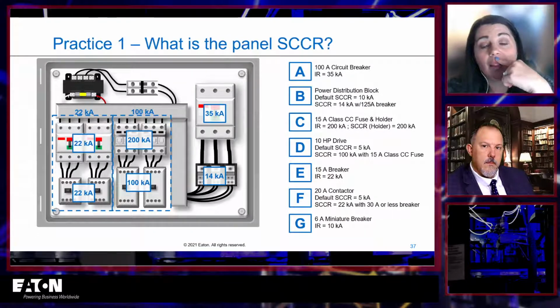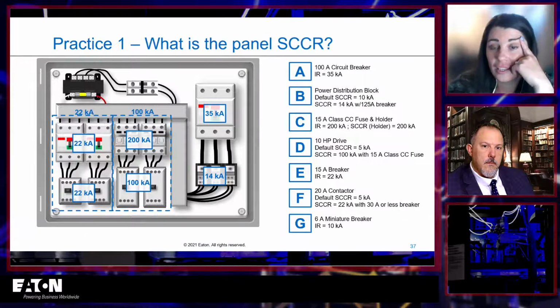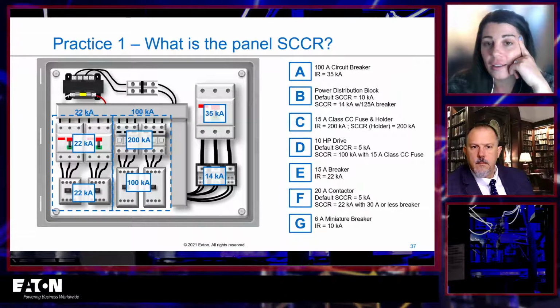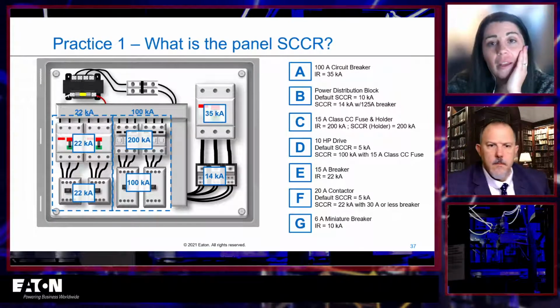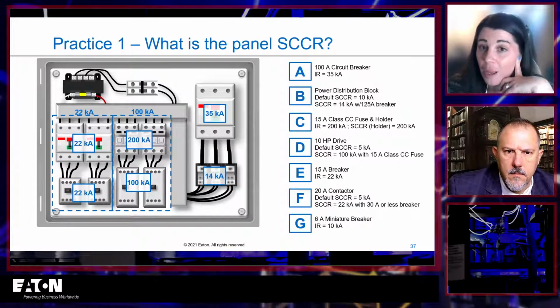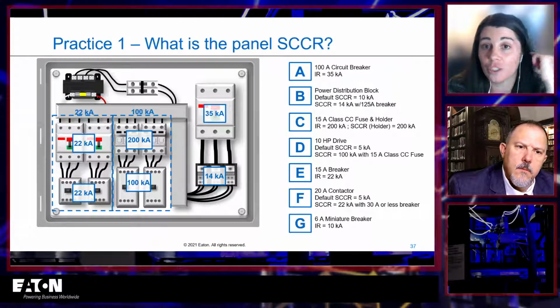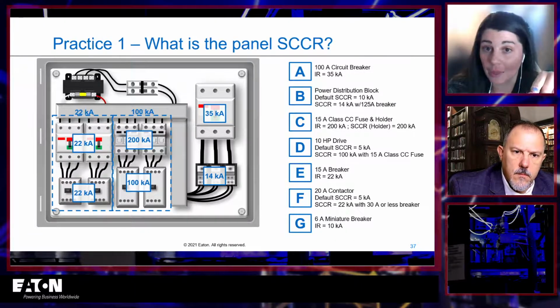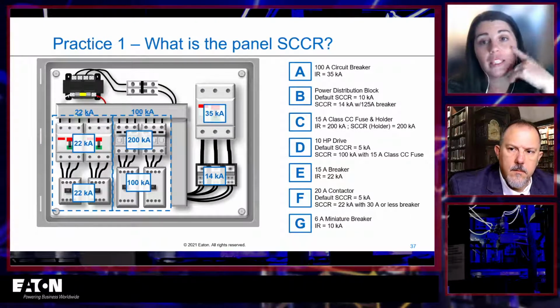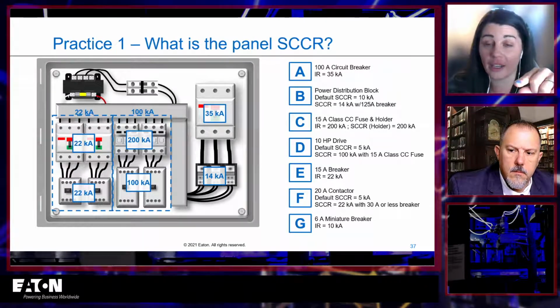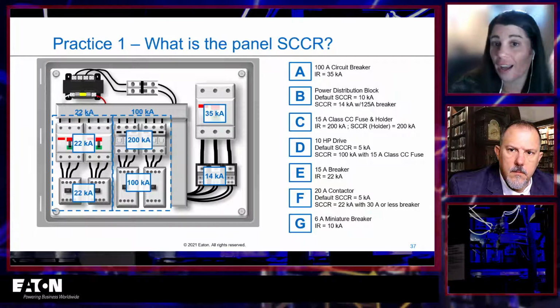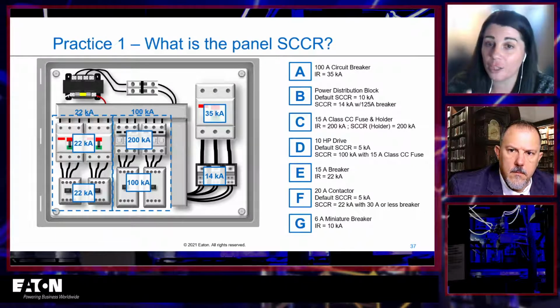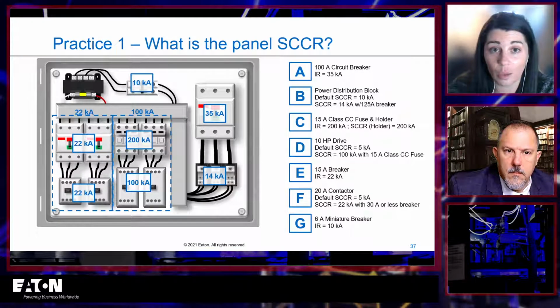And then what I have to remember, and this is a somewhat commonly forgotten thing inside my panel, is the primary protection for my control circuit. Whether I'm going to a transformer or a power supply, it could be either a 2-pole or a 3-pole device, depending on that. That counts towards my short circuit current rating. So even though I get to ignore everything in the control circuit, I have to include the primary protection before I get there. In this case, that is G, this little 6 amp 2-pole miniature circuit breaker with an interrupting rating of 10 kA. I want to make sure I include that.